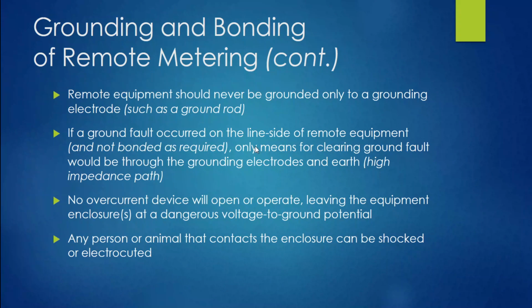That becomes a hazard. Okay, now I'm permitted to have some kind of grounding electrode in the remote meter if I want to, but I can't do it in lieu of the connection at the actual service equipment. Now, the reason I say it's permitted is, to be honest with you, it is done all the time at the utility when they drive them at the pole. Okay, it's connected to the grounded conductor. So the secondary side of the transformer has that connection that's connected between the actual winding, a midpoint of a winding to ground, and a grounded AC system is connected to the earth. So all you're doing at the remote equipment is doing the same thing as you would do at the service equipment.